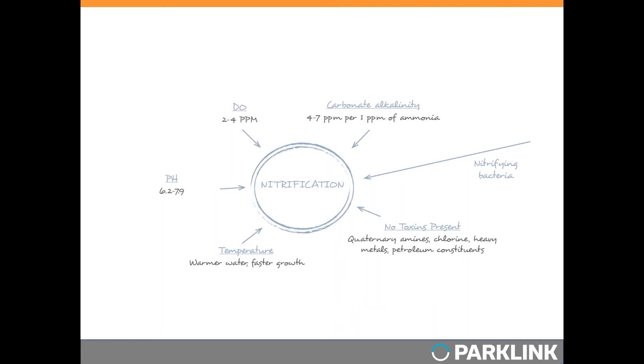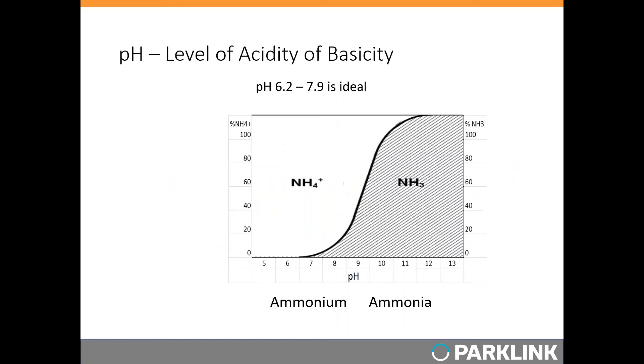The next stop on the nitrification wheel is pH — the level of acidity or basicity in your treatment plant water. Nitrifying bacteria generally work best at a pH of 6.2 to 7.9, with around pH 7.2 being optimal. Ammonia oxidation produces acids, and too much acid dropping the pH to around 5.5 will inhibit further ammonia oxidation, though they can recover. Ammonia-oxidizing bacteria will become dormant or die at pH greater than 8.5.